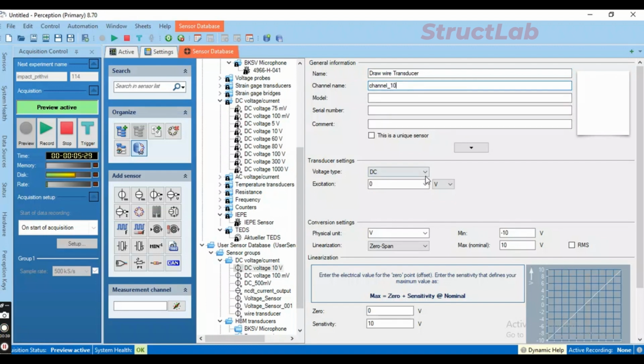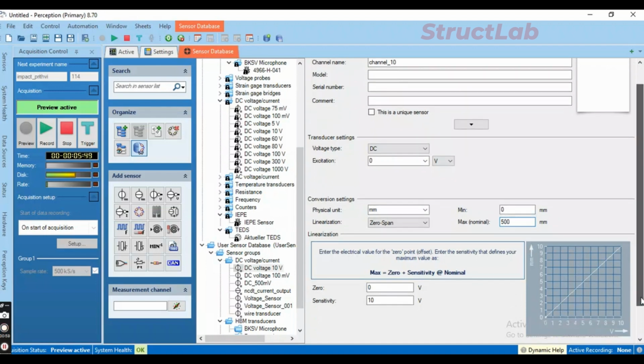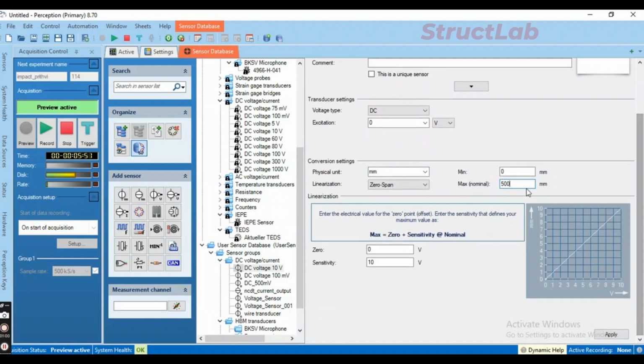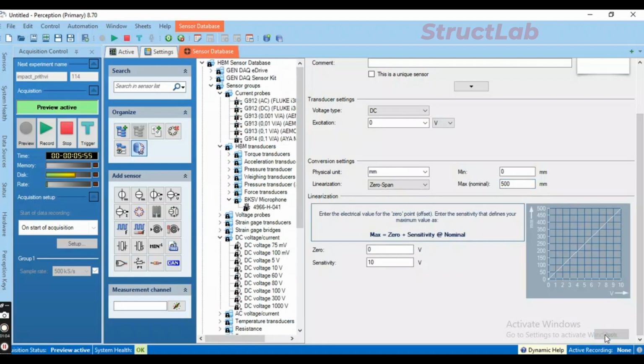Next, move down to Transducer Settings. Since the sensor is powered by an external supply, set the excitation voltage to 0 volt. Under Conversion Settings, change the physical unit from volts to millimeters. Set the conversion range from 0 millimeters to 500 millimeters to match our draw wire's total displacement span. Check the linear scaling curve generated in the bottom right plot, mapping 0 to 10 volts directly to 0 to 500 millimeters. Click Apply to save this sensor configuration into the database.